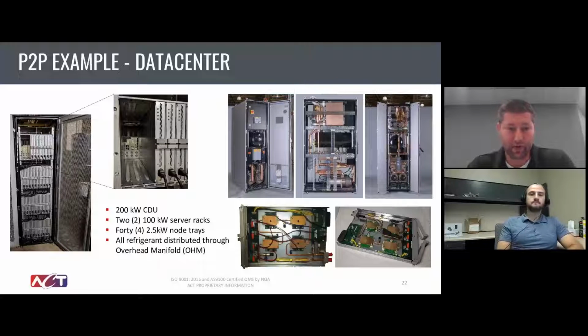All of those operated in parallel flow between the different blades that went into the server, and then serial flow within the blade. Each blade had 4 different evaporators on it, but the entire system ran in parallel flow. Again, 200 kilowatts, fairly complex circuitry, but pump two-phase does allow you to design in a lot of parallel flow channels, and as long as we understand what the end use is trying to do, we can develop it so that it can be controlled passively in most cases.